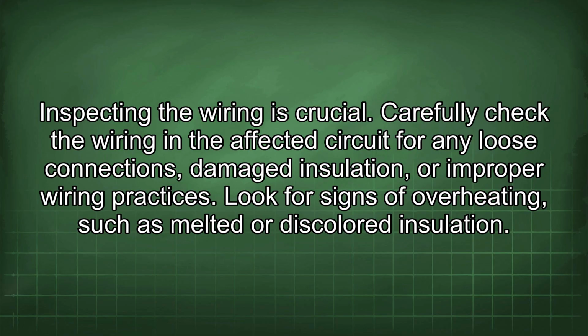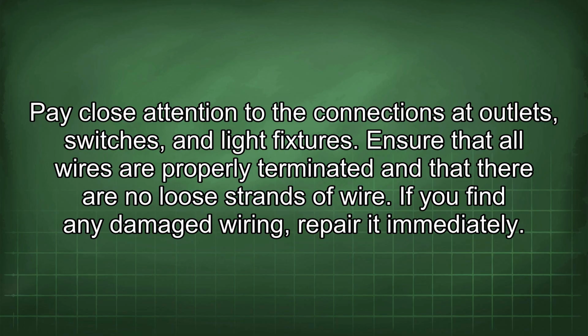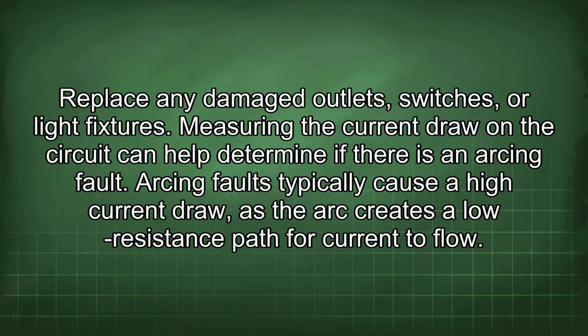Inspecting the wiring is crucial. Carefully check the wiring in the affected circuit for any loose connections, damaged insulation, or improper wiring practices. Look for signs of overheating, such as melted or discolored insulation. Pay close attention to the connections at outlets, switches, and light fixtures. Ensure that all wires are properly terminated and that there are no loose strands of wire. If you find any damaged wiring, repair it immediately. Replace any damaged outlets, switches, or light fixtures.